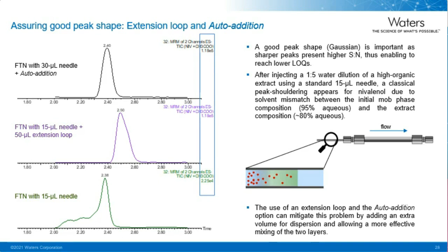and gives distorted peaks. 2 potential solutions when using an FTN are the inclusion of an extension loop to add more volume for an increased dispersion, like in the middle chromatogram, or to use the auto-addition functionality, where the sample is co-injected into the system with a fixed volume of water and an additional mixing occurs inside of the needle. Both options lead to much better peak shape.